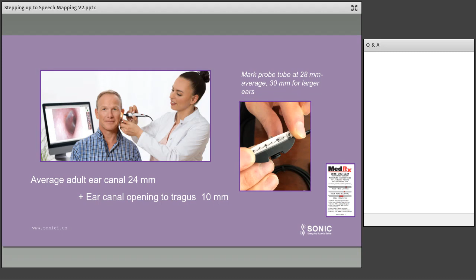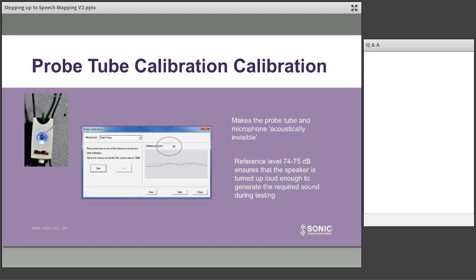It's also important, just like any other real ear measure, that you calibrate your probe tube. Probe tube calibration is very important. We know that each probe tube has its own acoustics, its own special variation outside of the norm, the standard deviation. And so when we calibrate our probe tube, we're going to see what those slight variations are, and we're going to make the probe tube acoustically invisible to the measurement. So if you're using your MedRx software and you're calibrating your probe tube, just make sure that when you're running the stimulus, the reference level here is about 74 to 75 dB. What that does is it tells us that the speaker is turned up loud enough to perform the test that you want to do.